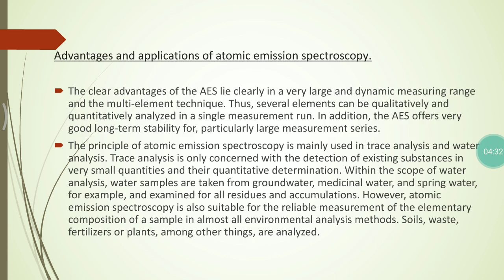Application. AES is also suitable for the analysis of highly radioactive samples as no interfering radioactivity is introduced in any part of the analyzer. In practice, 60 elements are detectable, in the 10 ppb range. It is used in determining the impurities of nickel, manganese, copper, and aluminum in iron and steel. In metallurgical processes, the percentage determined is 0.001% in iron to 30 in steel. Lubricating oils can be analyzed for nickel, ferrous, and manganese.